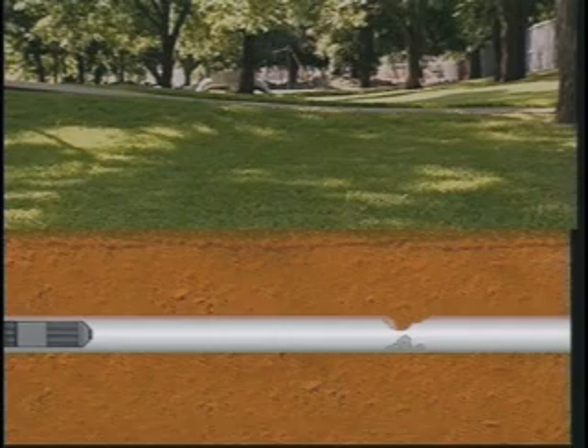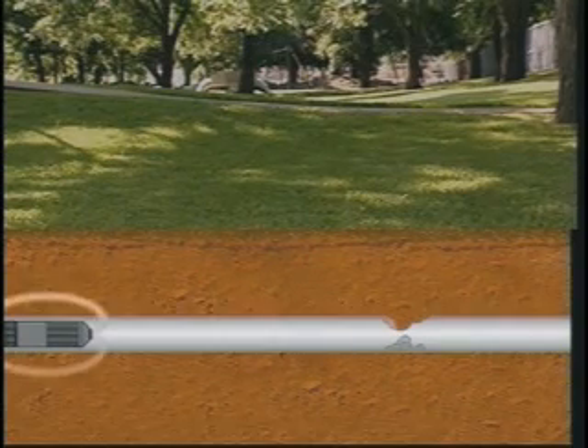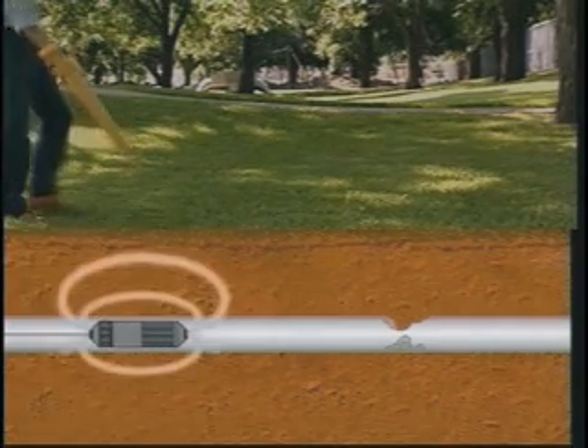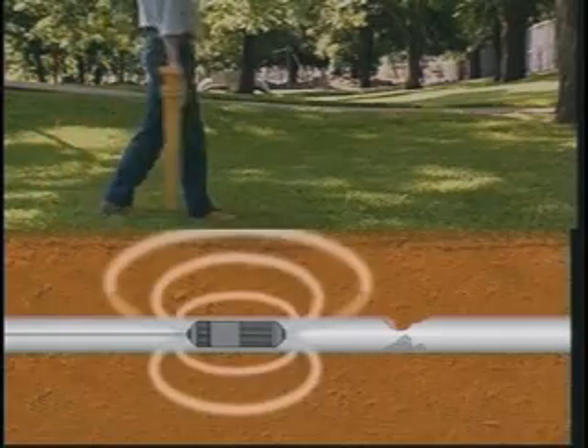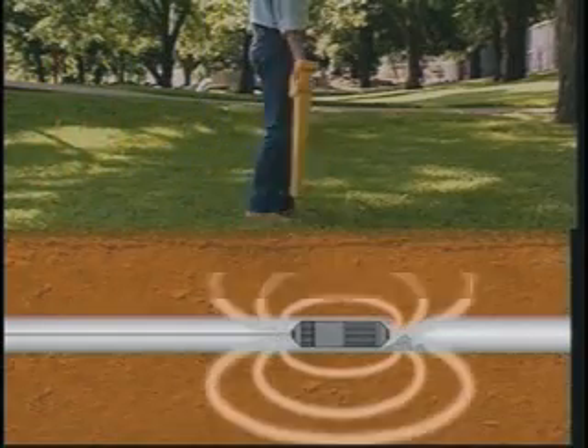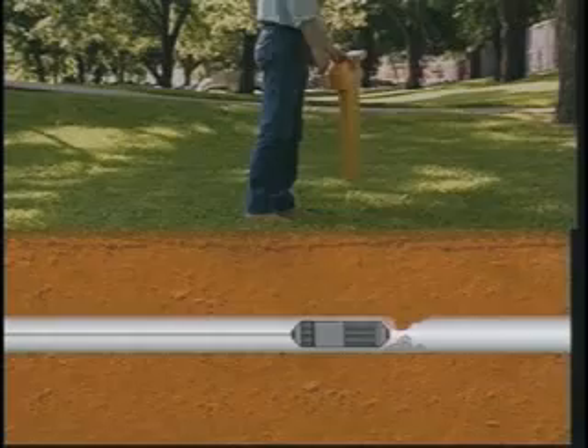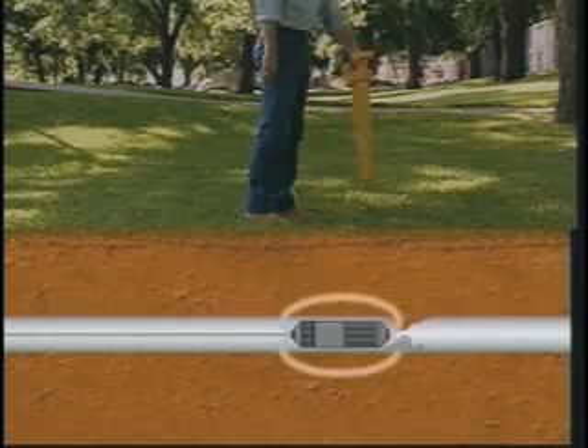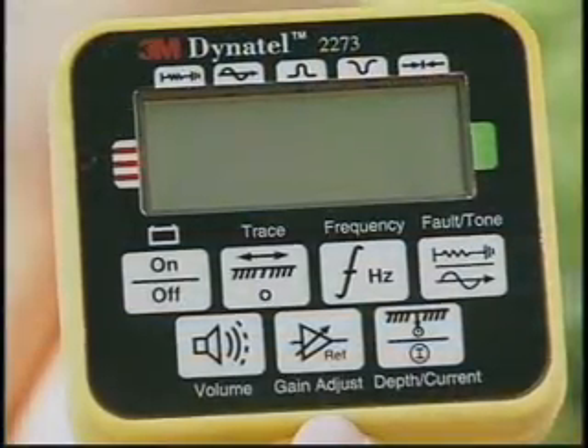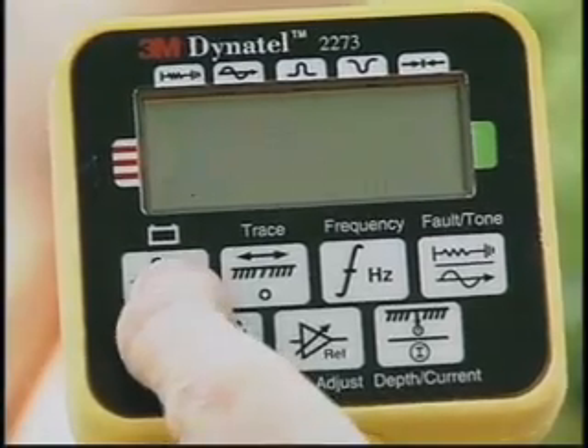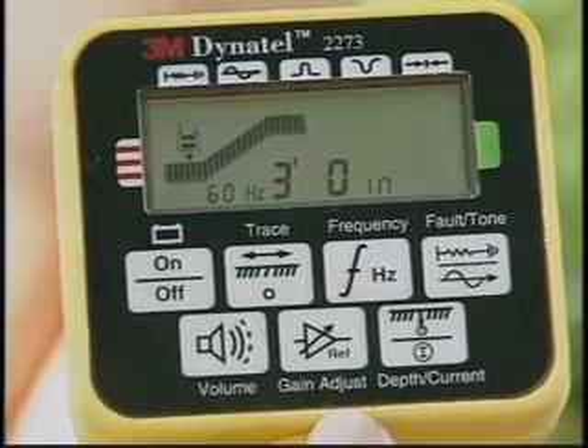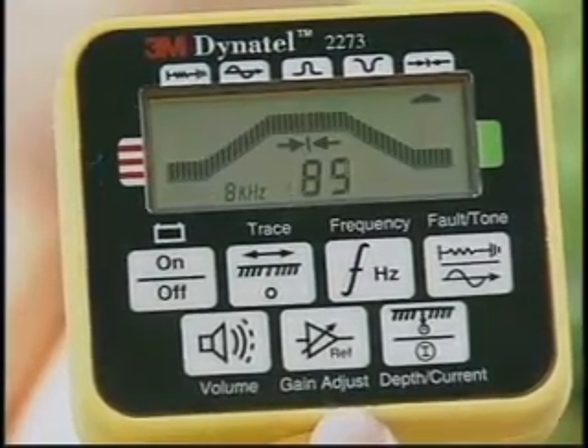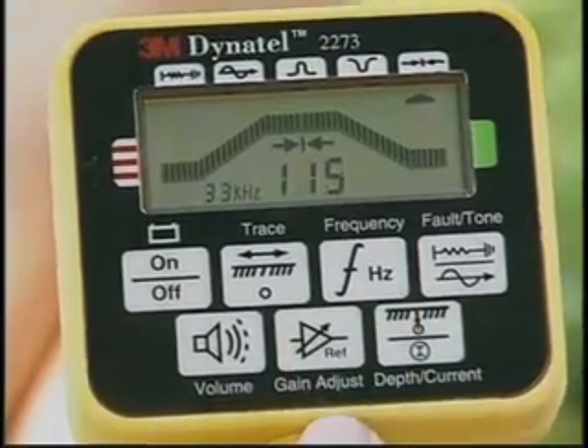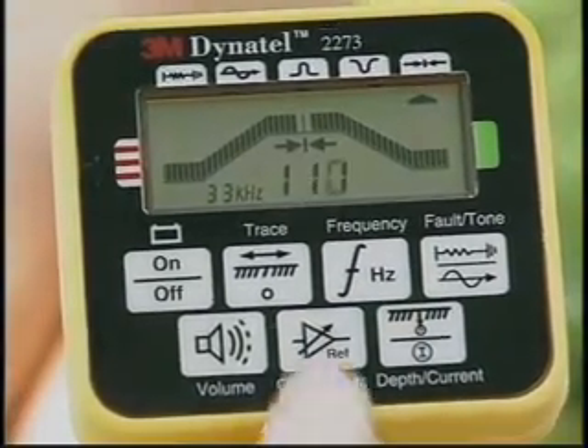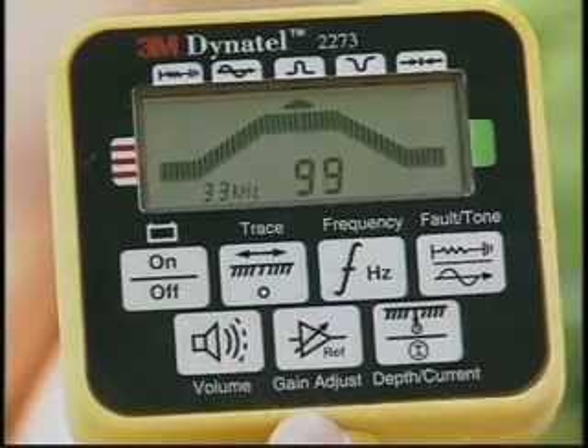When a non-metallic pipe becomes obstructed, a 3M active duct probe is a convenient device that's used to locate the problem. The probe emits a signal that the receiver can detect, allowing you to locate it. To locate an active duct probe, turn the receiver on, select the ADP frequency, which in this case is 33 kHz, then select the peak trace mode.